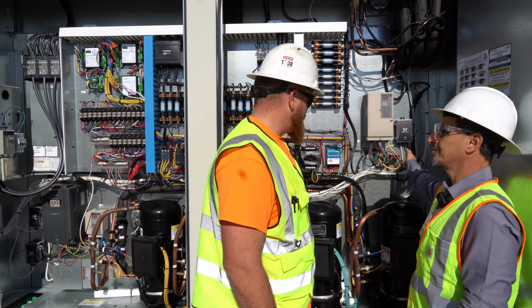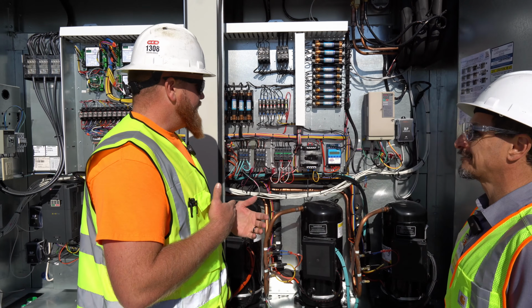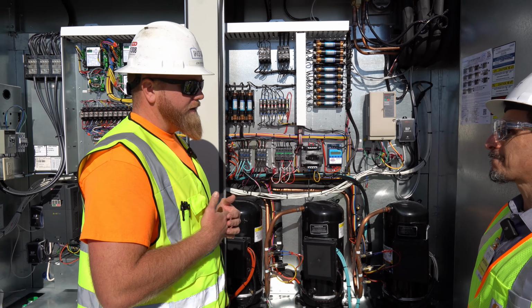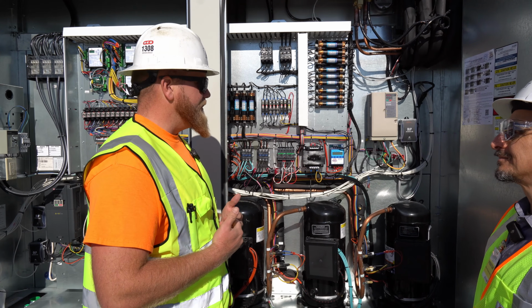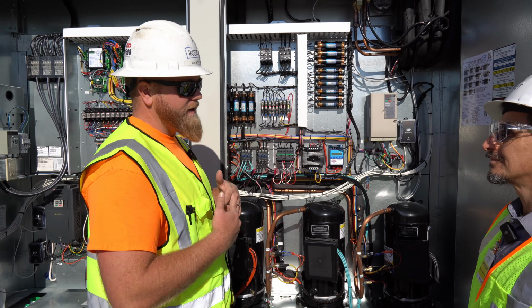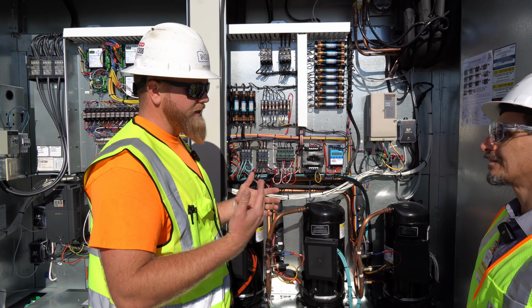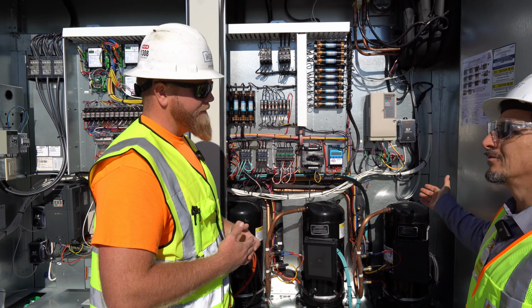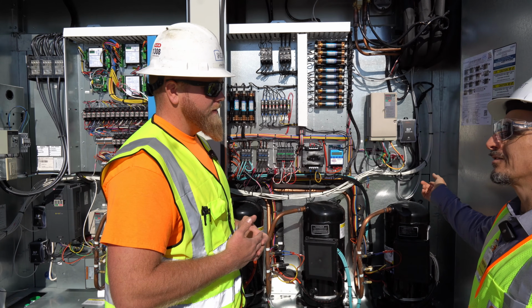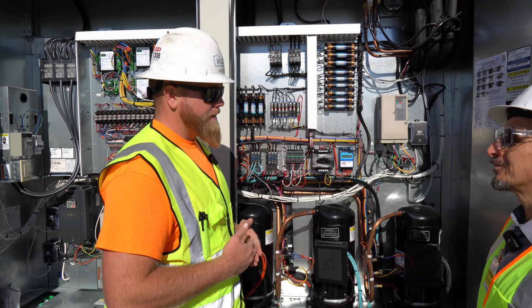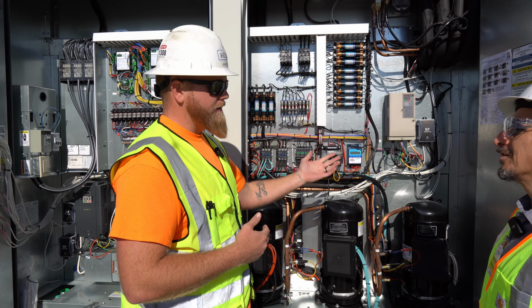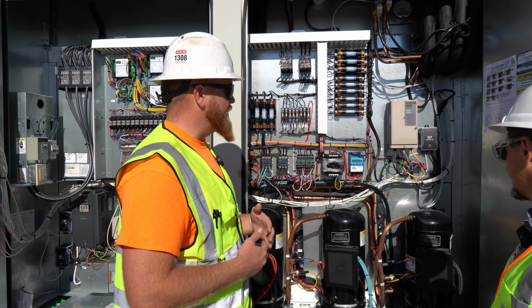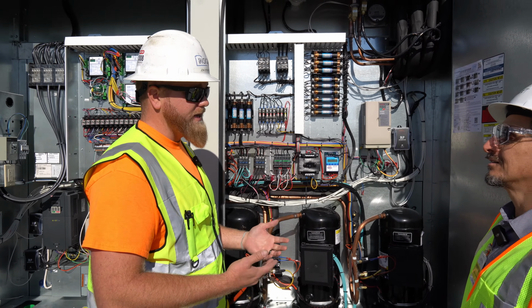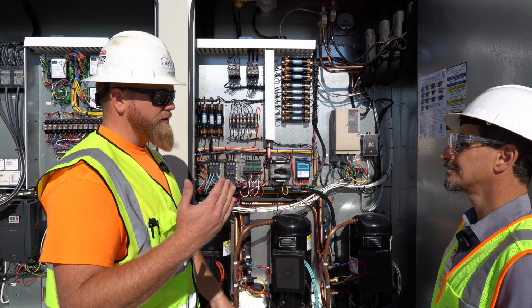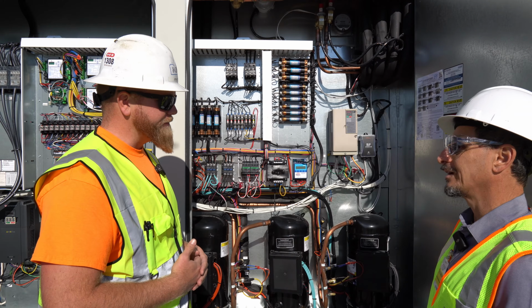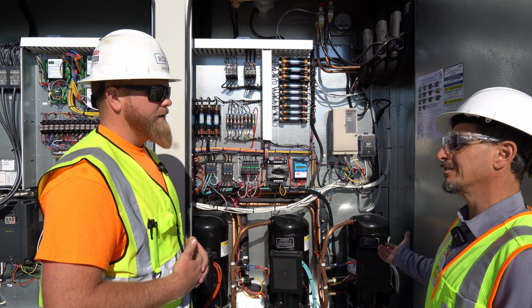Why is this important to have? We use that basically as a confirmed on-off feature of the fan. So even though we're getting the feedback from the fan, that shroud could have come off, the blades could have come off, and that fan's still sitting there running, but it's not pulling any draw. So if it's not, then we know it's not. There's something going on that's wrong. We call it a proof of flow. We know that the energy is going to the fan motor. The VFD's proven that. We'll see the duct static react to that contact closure. We'll be able to verify that the fan is turning on. Right, because we're calling for a component to run doesn't mean it's actually running.